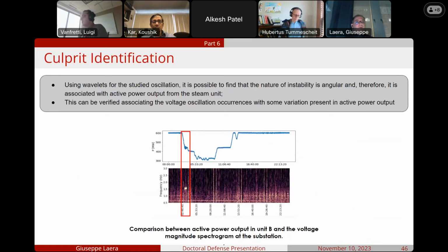So now that we know that unit B is responsible for this oscillation, the first idea is to find some sort of event that triggers the oscillation. And by the use of continuous wavelet transform, it is possible to find that the nature of the instability is angular, and that means it is associated with active power output from the steam unit. So we can see the plots show a comparison between the active power, the power output calculated from PMU data, and the spectrogram of the voltage magnitude at unit B. And the window highlighted in red shows that the oscillation around 1.54 Hertz appears as soon as the active power output of the unit drops from 600 megawatt to approximately 420.